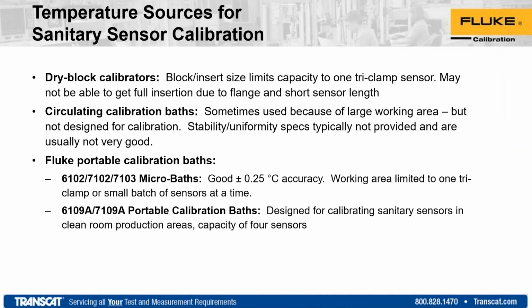I mentioned dry blocks are somewhat limited, due to the design around what they typically work best for, which is the more traditional sheath probes. Second, typically due to the size of the inserts or block assemblies, you can only do about 1 with any dry block, and it's going to have to be a TriClamp that's fairly long with the stem length. From that picture, if you recall a few slides back, a lot of these are fairly short, maybe only 2 to 3 inches in length. So you run into some potential issues using a dry well.